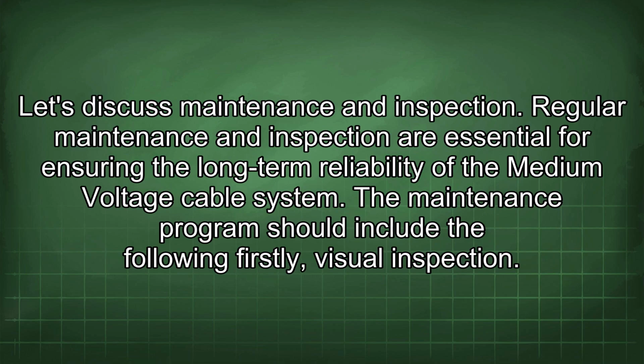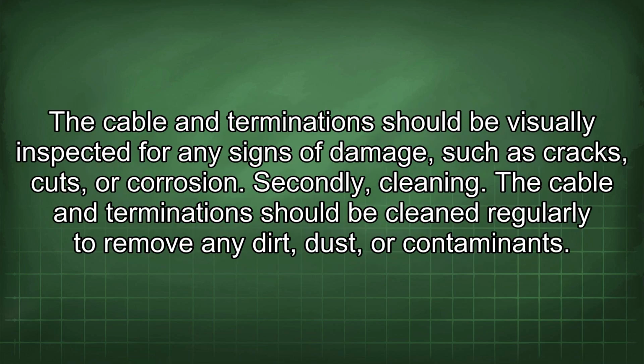Let's discuss maintenance and inspection. Regular maintenance and inspection are essential for ensuring the long-term reliability of the medium-voltage cable system. The maintenance program should include the following. Firstly, visual inspection. The cable and termination should be visually inspected for any signs of damage, such as cracks, cuts, or corrosion. Secondly, cleaning. The cable and termination should be cleaned regularly to remove any dirt, dust, or contaminants.